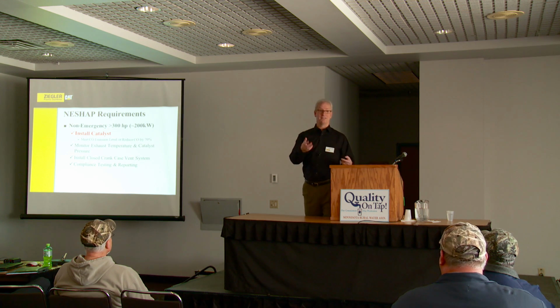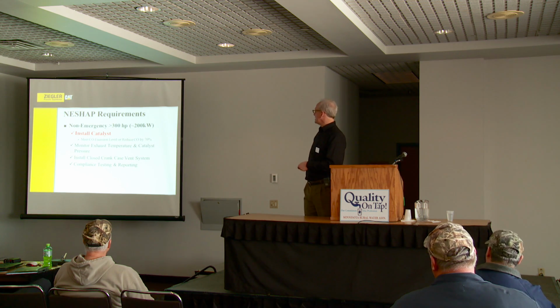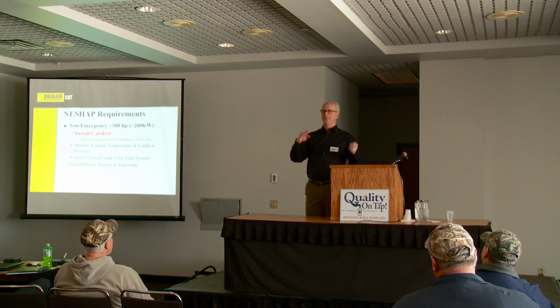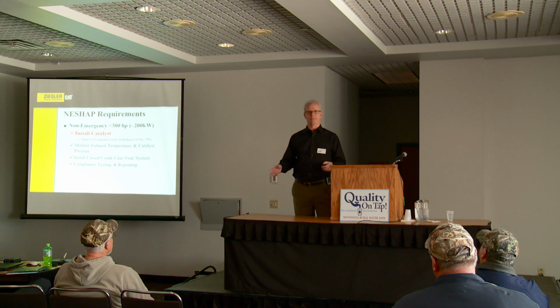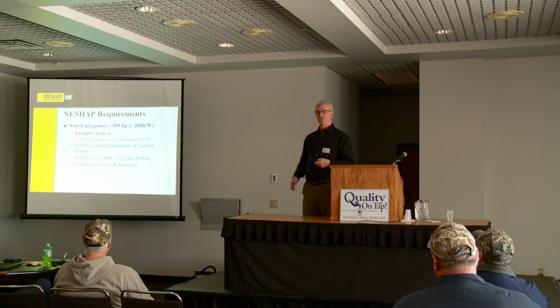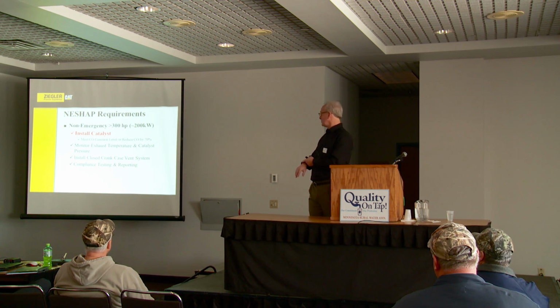That's just the part that says I really know what I'm talking about, but it's way too much information. But generally, it's reduced by 70%. So whatever your engine puts out, 100 parts per million, you put a catalyst on, and now it puts out 30 or less, you've reduced it by 70%. You also need to have a monitoring system, monitoring the temperature and pressure on the catalyst to make sure your emission system still works properly.